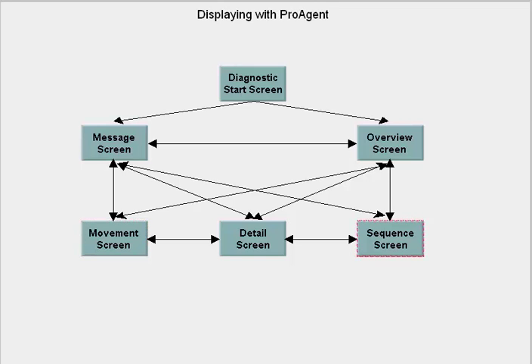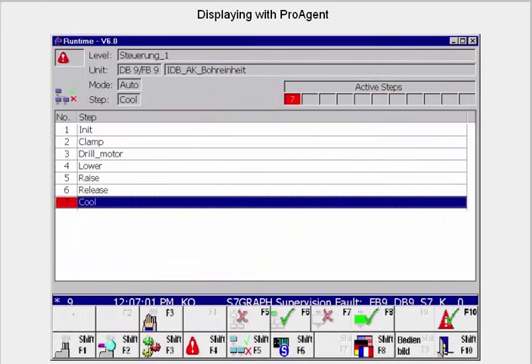If there is an S7 graph sequencer behind a faulty unit, you get a display of the steps and at which step the sequencer is at the moment. The sequencer can be initialized from here, or you can enable or disable a specific step.